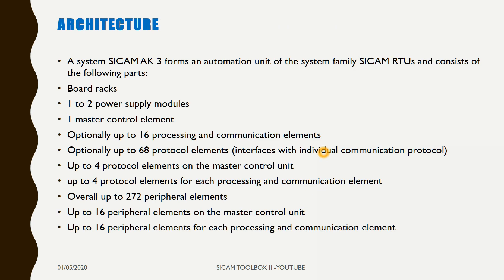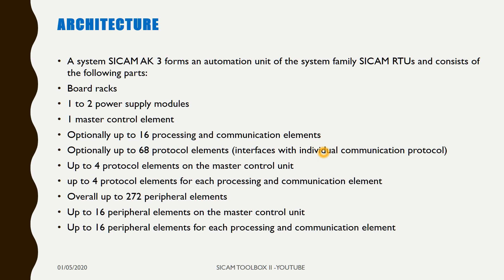It serves for the equipment of basic modules and peripheral modules. An automation unit consists of the following parts: board racks, two power supply modules, one master control element, 16 processing and communication elements, 68 protocol elements — which are used to interface with individual communication protocols like Modbus, PROFIBUS, IEC 101, IEC 103, IEC 104, IEC 61850, DNP — four protocol elements on the master control unit, four protocol elements for each processing and communication element, and overall up to 272 peripheral elements: 16 peripheral elements on the master control unit and 16 peripheral elements for each processing and communication element.